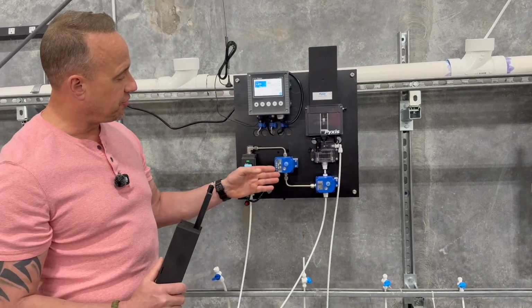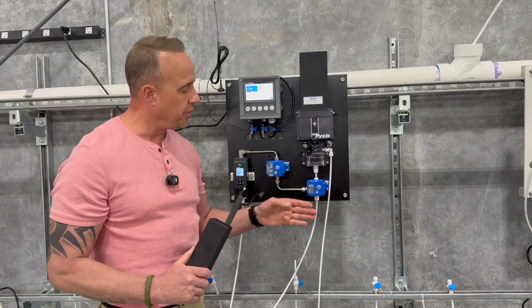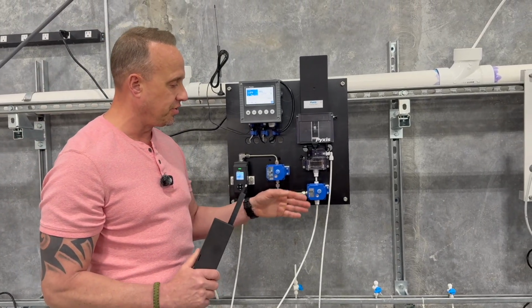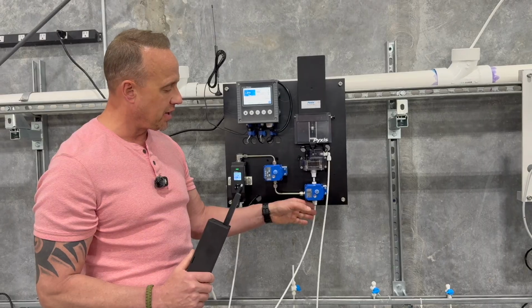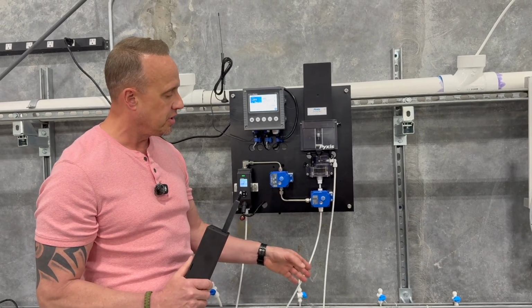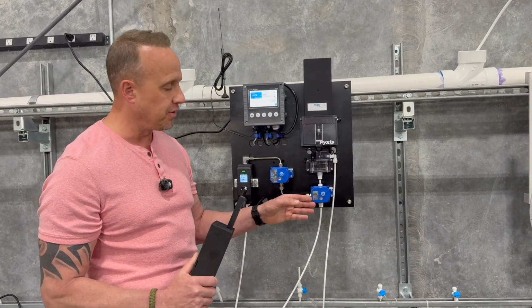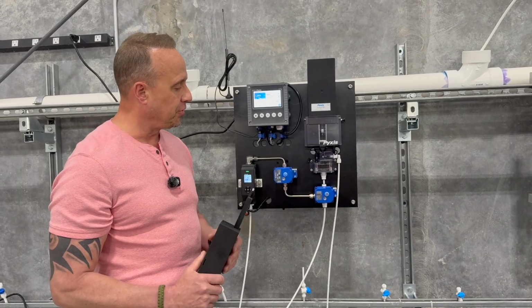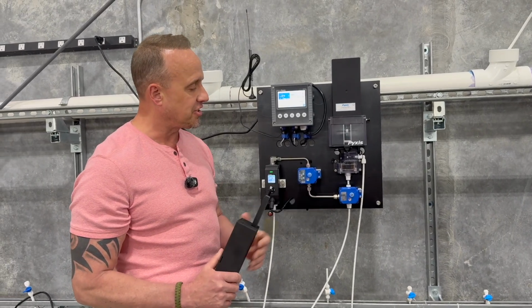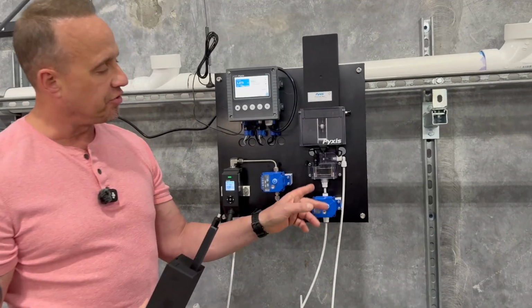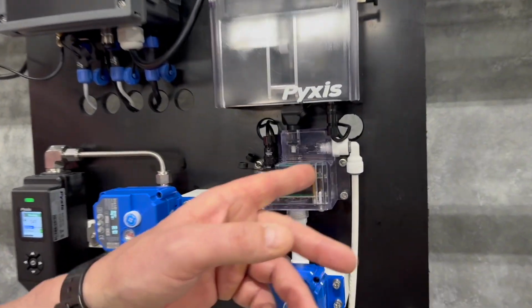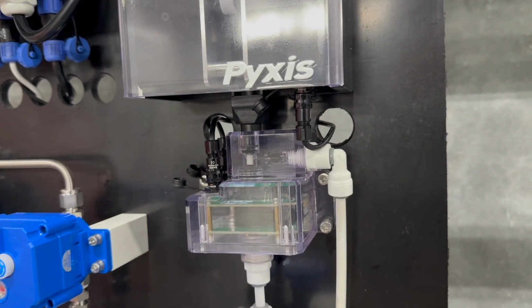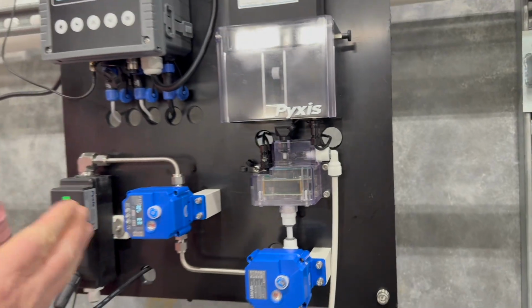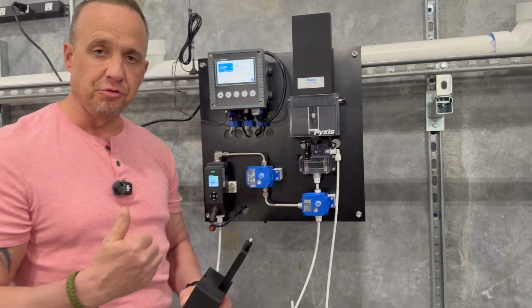Once the sample passes through the motor valve, it hits a 3-way valve. The 3-way valve, when in standby mode, is just sitting idly by, allowing either the sample to go to drain in standard operation or closed in a water savings mode. And then when it comes time for the sample to actually obtain in the reaction chamber, the 3-way valve will open, the water sample will flush the reaction chamber and go to overflow to drain for a set period of time. That can be manipulated by the customer and their user preference.